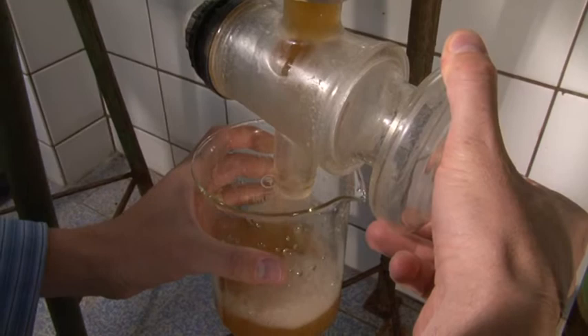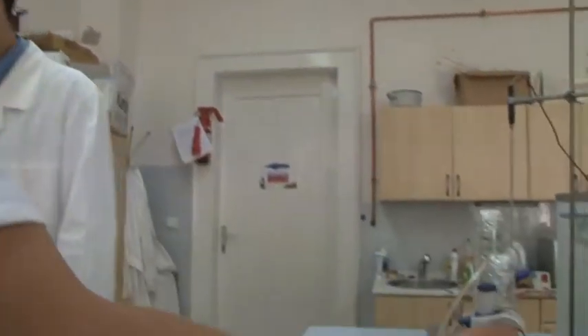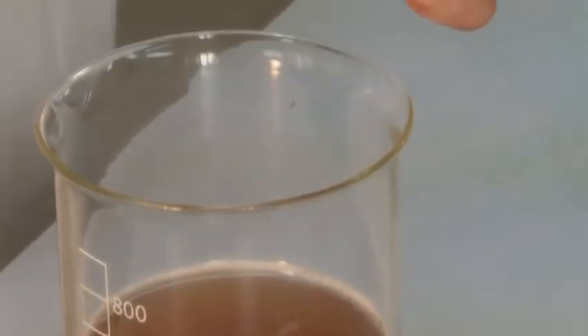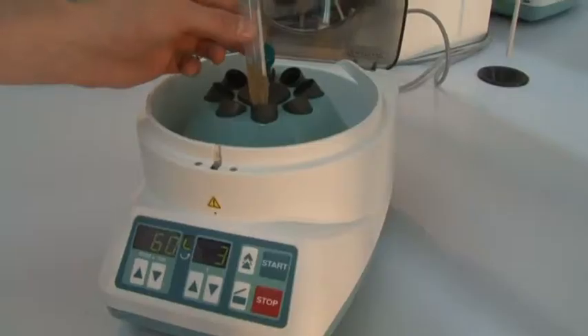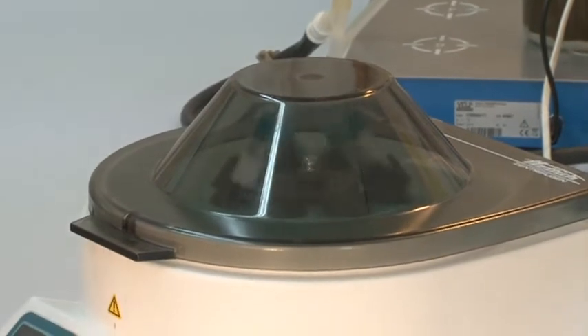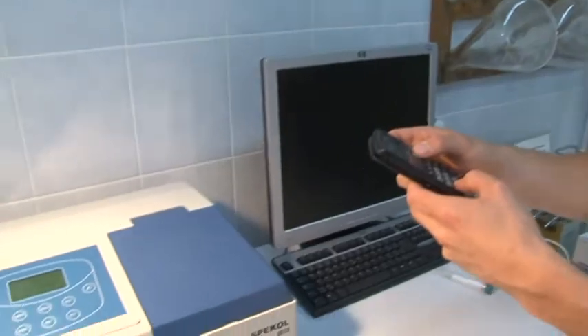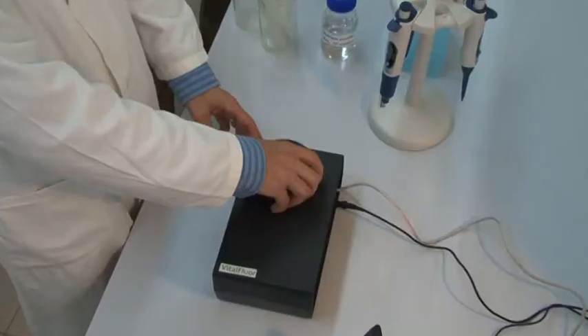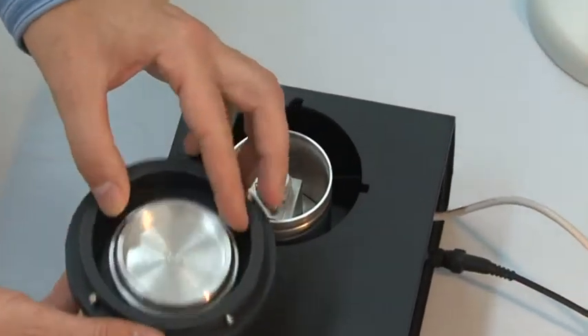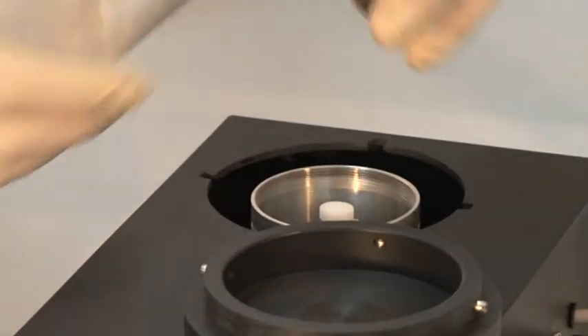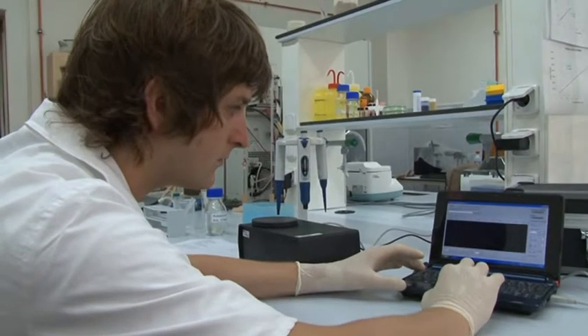The measurement procedure will be demonstrated on brewing yeast. Prior to the vitality measurement, the cells are suspended in a physiological solution to a constant concentration determined through optical density. The suspension in the closed measuring cuvette is placed into the VitalFluor. After feeding the sample name, the measurement is started.